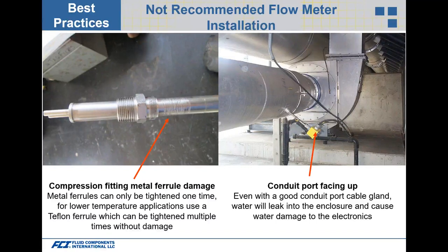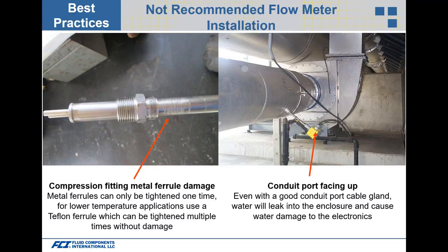Another issue: the electrical conduit port or cable gland facing upward. You don't want this because water can leak through the cable gland — even the best cable gland can allow water damage to the flow probe electronics.